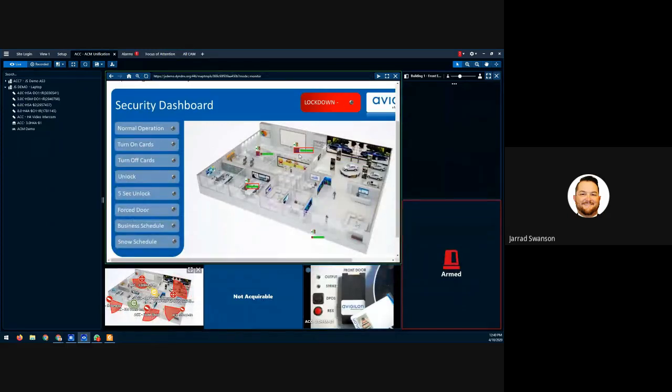It took doors that were in my system and put them into priority card only mode. So if those doors were unlocked, they're now locked. They're now in a card only mode. It uninstalled all of my teachers' or normal employees' access groups, and it installed a group of first responders' cards. It is linked to cameras on my system. So once again, in an operator's view, if they had a view of all of their cameras and they saw every single one of their cameras start flashing red all at the same time, they would know that something bad, something really bad may have happened.